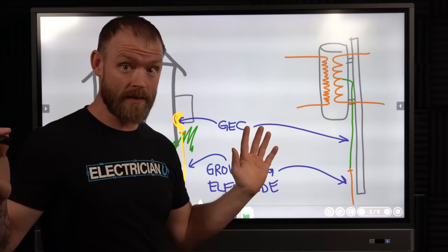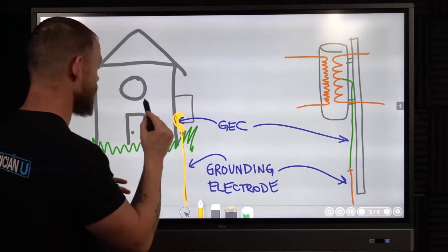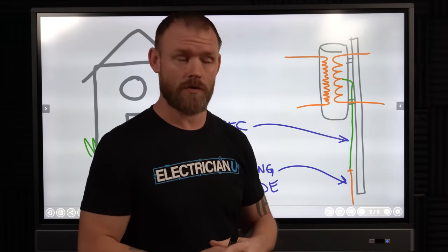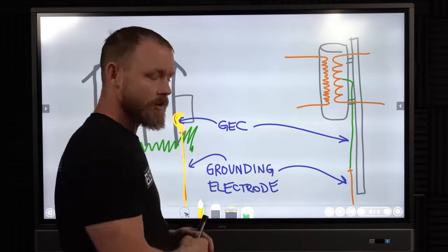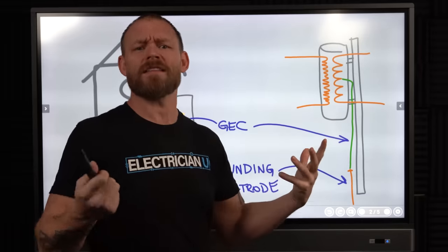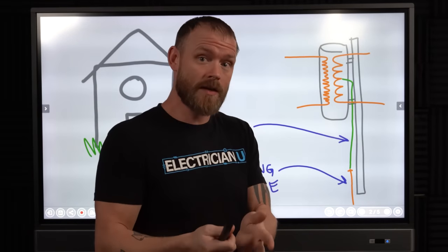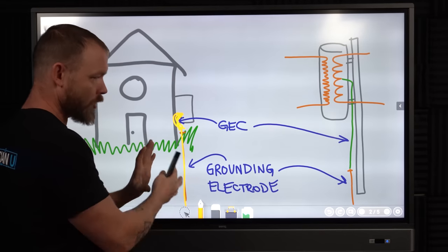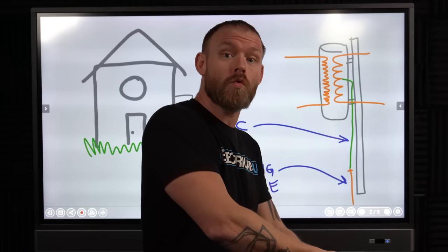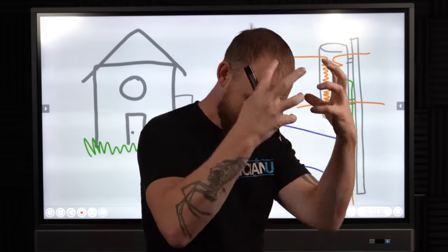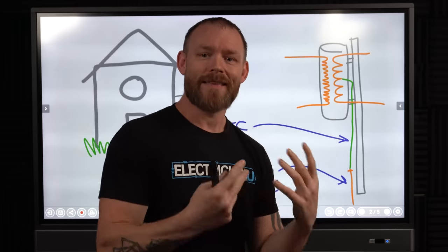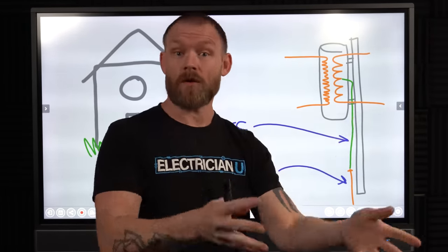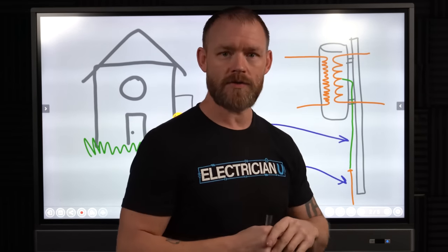Electrodes can be a lot of different things. Looking at Article 250 in code, they talk about metal underground piping systems, large metal underground structures, ground rods, ground plates you can bury — all kinds of things you can use as a grounding electrode. Sometimes we use the rebar in a slab. The conductor you run to that large piece of metal to establish continuity with earth is the grounding electrode conductor, and its purpose is entirely different from equipment grounding conductors, or EGCs, which we'll get to in a minute.